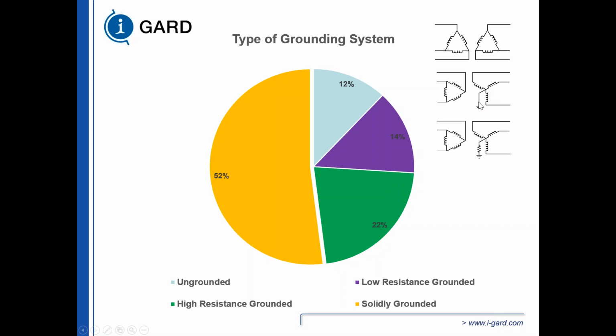And a solid grounded system, because most people think it's economical to put in a solidly grounded system, so they choose that. And what we find is there are some people that put in a solidly grounded system who work from a specification and then turn over the property to an end user who is going to maintain that property. If the two parties worked hand in hand, and the people who built the property and the people who maintain the property work together, I'm sure they would come up with a better grounding system. But one is looking at, I'm sure you've heard about this before, green dollars and blue dollars. One is capital, one is maintenance. And if the two actually met, they would compromise and come up with a better solution, which is, I feel, most likely the high resistance grounded system.